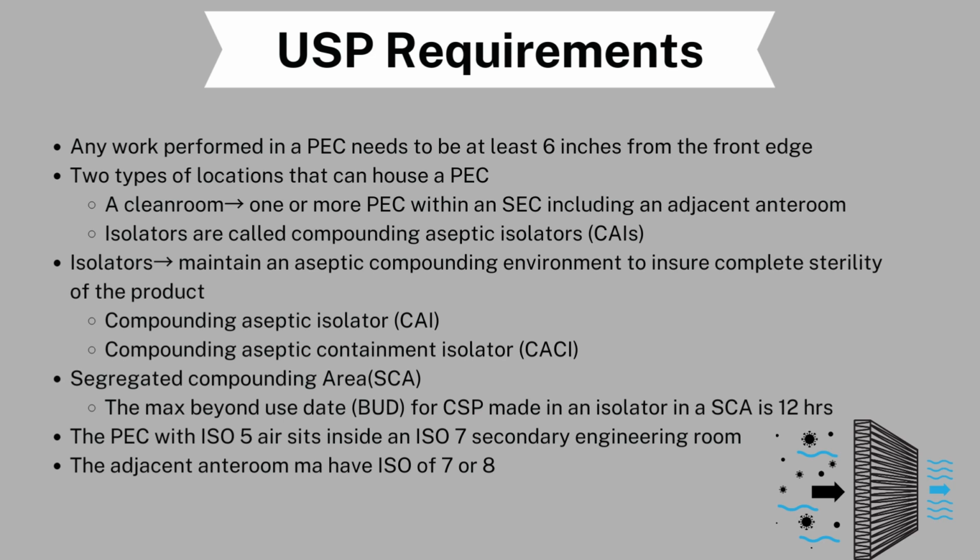There is a segregated compounding area. The max beyond use date for a CSP made in an isolator in an SCA is 12 hours. The PEC with ISO 5 air sits inside an ISO 7 secondary engineering room, and that adjacent anteroom may be an ISO 7 or 8.